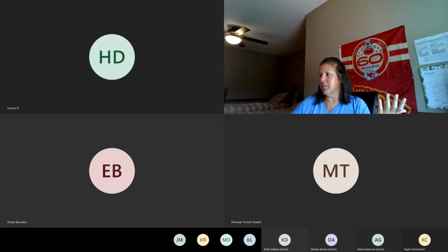Radiation monitoring is just the monitoring of your equipment, which should be evaluated regularly for leakage radiation. The radiation monitoring badges that you wear will absorb any radiation that you may be receiving while you're working in that environment. Those little badges are sent in at a specific time interval, and it's cumulative. So they keep a running history.